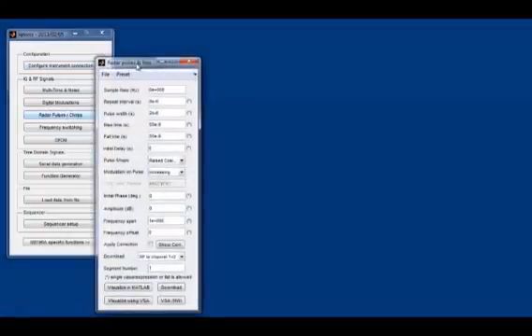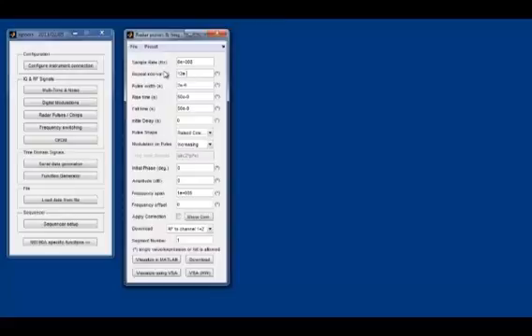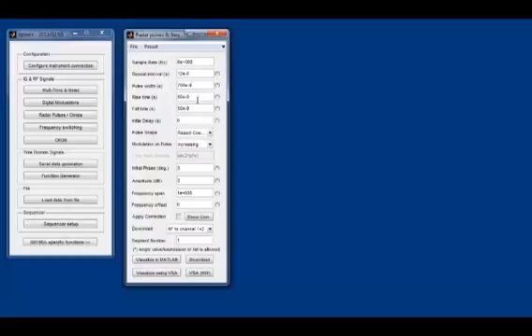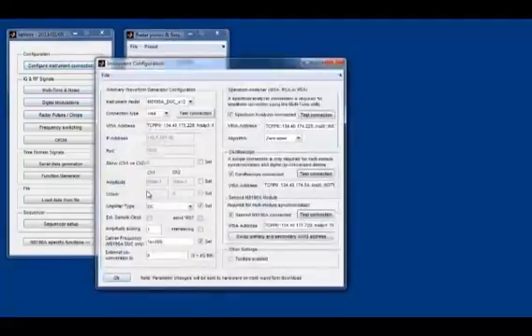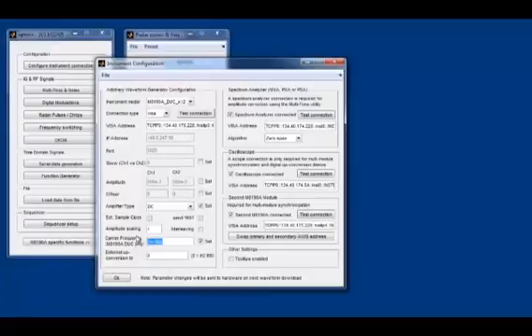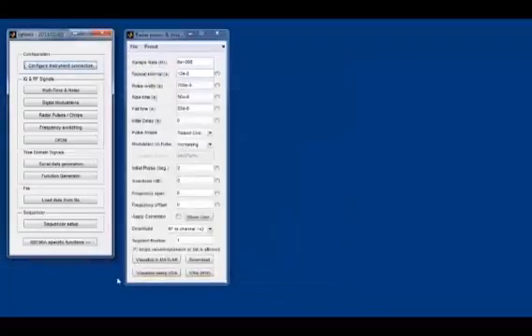In the second part of my demo I want to show you how to change phase of a signal under sequence control. For that I'm going to use a radar pulse signal. I change the repeat interval to 12 microseconds and I change the pulse width to a pretty short 700 nanoseconds. The reason I'm doing that is because I want only a few periods on the screen. I want to capture this with the oscilloscope, and I put my frequency span to zero which means I'm generating a CW signal. I also change my carrier frequency to a very low 10 megahertz. Obviously this can be higher, but I want to have only a few periods so I want to use a very low frequency here.